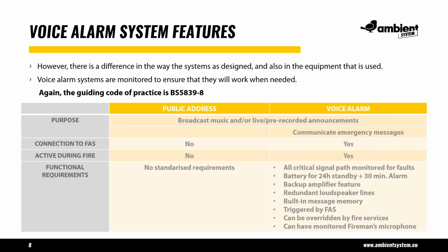The voice alarm system, the primary purpose in investing that extra money is to communicate emergency messages, and it will be connected to the fire alarm system and it will be active during a fire event. And the functional requirements that make that possible are effectively the information that we've listed at the bottom there.